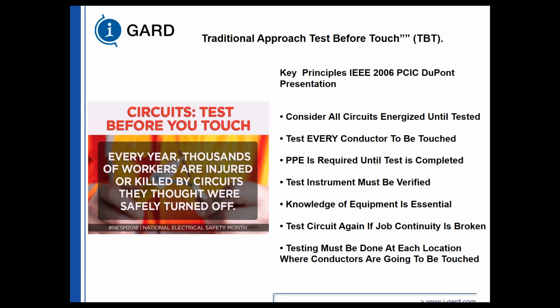Test instruments must be verified. Obviously, you have to ensure that your test equipment is working properly, to verify that the meter is working, to verify the absence of voltage. Knowledge of the equipment is essential. Test the circuit again if job continuity is broken.